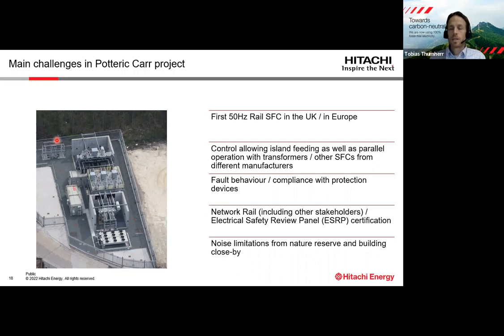Then always important is the fault behavior of the static frequency converter to ensure the continued supply of the railway system, and we have to comply with protection devices to make sure that they can properly react and isolate the fault. And because it's the first project in the UK, there was quite some need for certification from Network Rail, but also for other stakeholders. And there was a noise limitation from the nature reserve that is very close by and from a building.